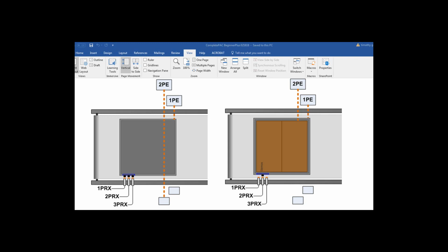And you'll see in the first tray there, when the first tray breaks the photo eye, in other words, breaks the beam of 1 PE, the tray is in a position for the 3 proximity switches to sense the absence or presence of that ferromagnetic bolt head.